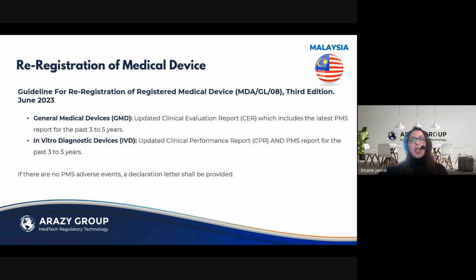So in Malaysia, since June 2023, the following requirements related to post-market surveillance were added for the re-registration or renewal process. For general medical devices, an updated clinical evaluation report, which includes the latest PMS report for the past 3 to 5 years, is now required for the renewal. And for IVD, an updated clinical performance report and PMS report for the past 3 to 5 years is also required in the process of renewal. And if there are no PMS adverse events, a declaration letter should be provided to justify that.